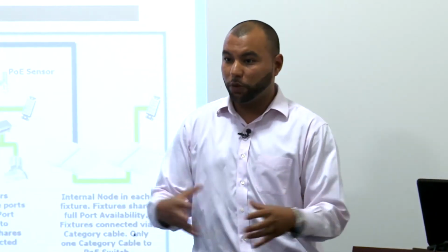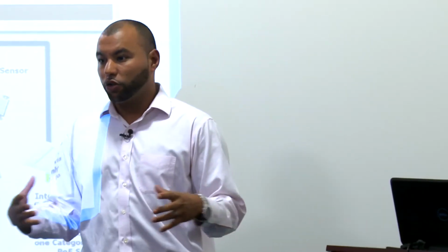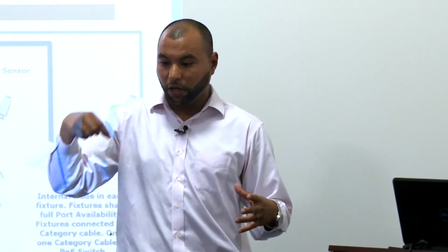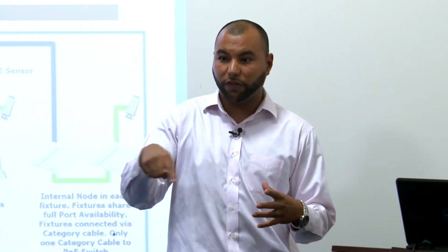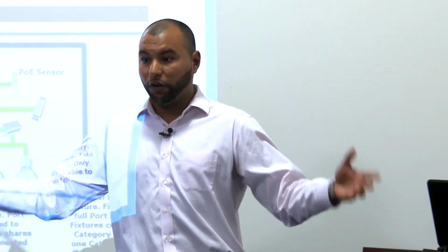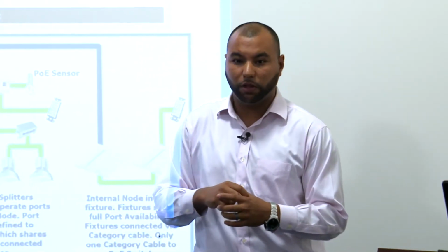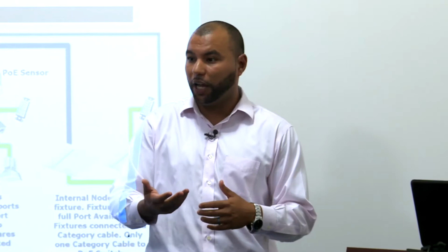The coverage area is pretty wide, about 16 feet diameter. So 16 feet diameter, if you place it in the middle, you pretty much cover more than one room. Typical rooms are 10 by 10, 13 by 10. You're going to cover outside of that. So speccing that particular microwave sensor might be a little tricky. Ask questions, we'll be able to help you.